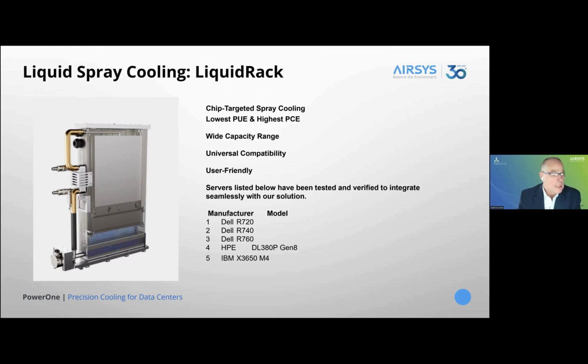And it goes back to the discussion I mentioned earlier about compressor free. We're looking at this as an important product set where the traditional design has been chiller, fan wall, CRAH, thermal expansion tanks, thermal energy storage tanks, and then to the rack itself. This eliminates all the mechanical stuff in between. So it goes from the dry cooler direct to the liquid rack, or the chiller, depending on your temperatures, direct to the liquid rack. And I believe that is, Jacques, the Power One portfolio from AIRSYS in a nutshell.